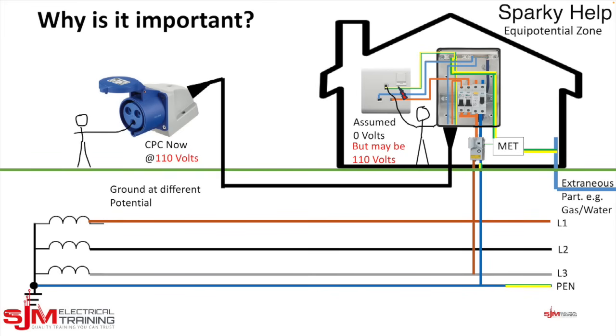Remember, potential is voltage. And in this case, they're actually very close to the transformer which supplied them in the first place, which has an added effect as well, because it's going to make the current path a little bit easier. So current can flow through that person and go to the star point of that transformer. Now, I'm not saying it's going to kill them, but you never know. It might be a slight tingling sensation. They might feel a bit weird. They might be running around in bare feet and feel a slight tingling through their feet because the ground's damp or otherwise. And therefore, this is potentially dangerous.